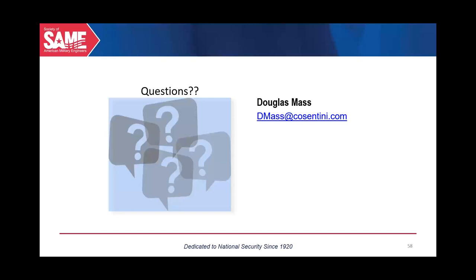Good. That answered a number of questions. A related question on UV lamps: is there an eye damage or vision damage risk with UVC lamps? The answer is yes, but we're only recommending them within air handling units themselves with a safety shutoff, or upper room UV. If you do upper room UV where the light shines up, you have to carefully select the materials to make sure there's no reflection down into the space.